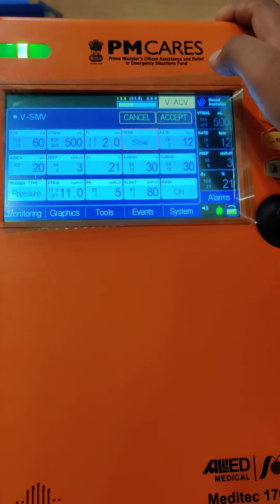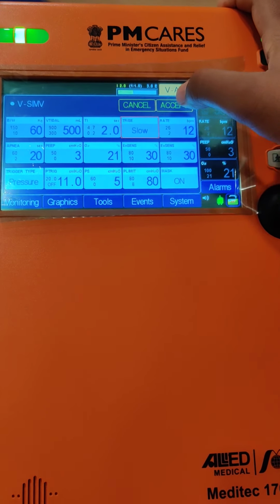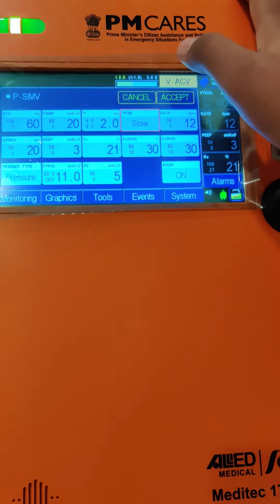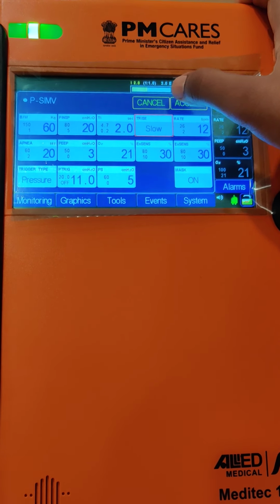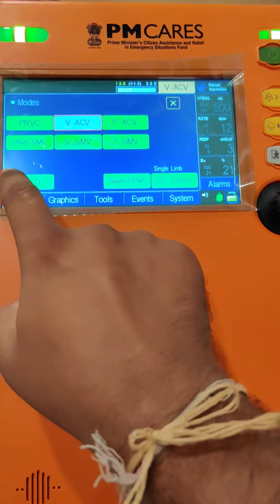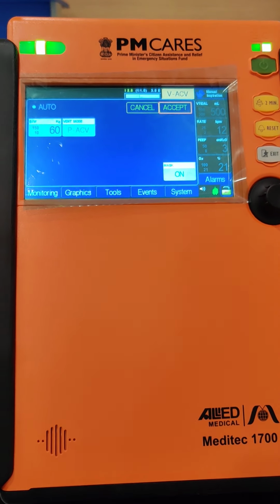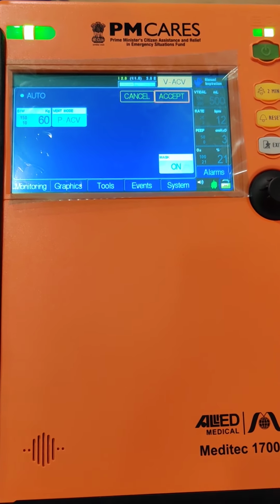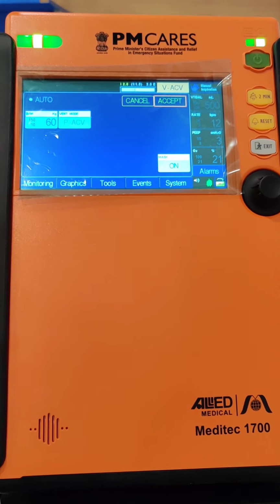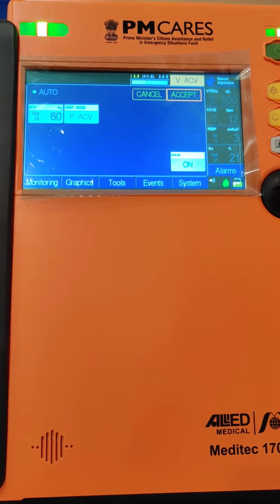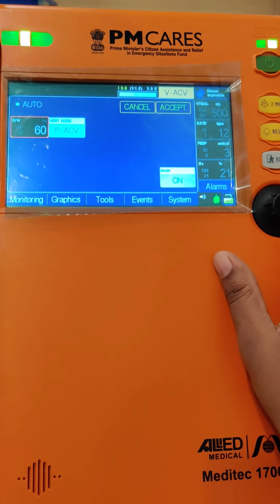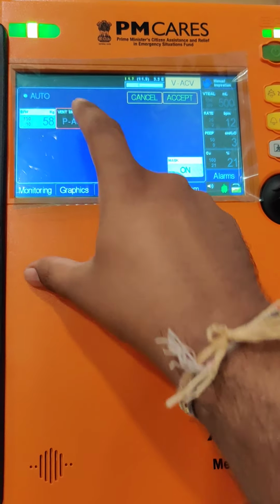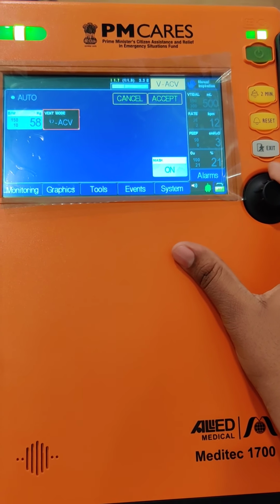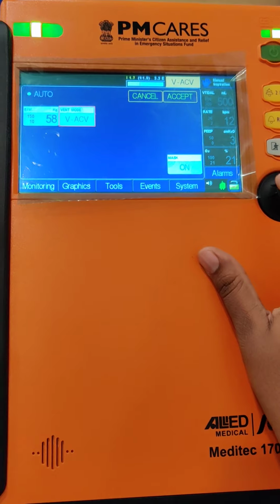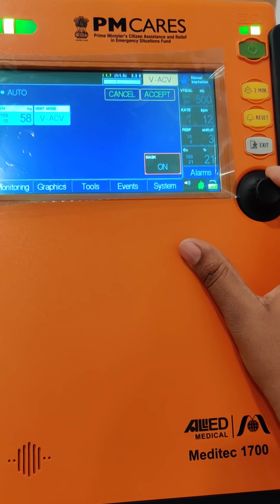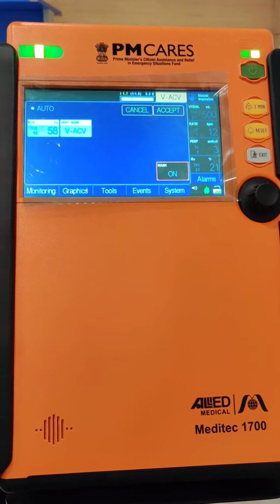Then we have this volume SIMV mode, and all these parameters you can set, and in the same way you have PSIMV, with all the parameters that are settable. And we have this very interesting mode of ventilation in this also. If there is some emergency and the staff is not available, or some doctor is not available, and some emergency case comes up, then in this mode you just have to set the body weight of the patient, and if you want to ventilate the patient on pressure control mode or volume control mode, that is settable, and you can set mask on or mask off depending on the intubated or non-intubated patients.